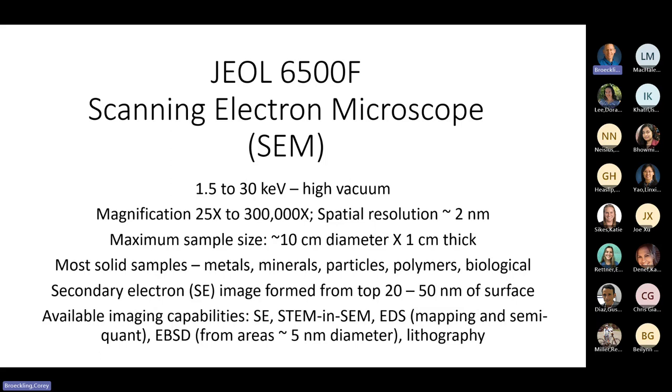The sample has to be solid - metals, minerals, particles, polymers, biological. For the most part, the SEM that we have now, we just do secondary electron imaging. That image is the top 20 to 50 nanometers of the surface. We can do STEM-in-SEM, EDS which is elemental imaging and mapping, EBSD which is electron backscattered diffraction, and lithography.